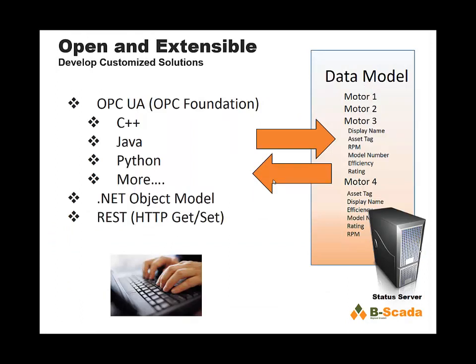What BSCADA has found over time is that once you have this model set up with live data flowing into it, it becomes extremely valuable to an organization. Companies always want to connect to that model with other pieces of software or with custom applications to subscribe to value changes or write information to the model. Because the core of the Status system is an OPC server, you can use OPC foundation libraries to connect to the model in C++, Python, or Java. BSCADA has also developed a .NET object model over top of OPC UA, and you can also use REST to get or set values within the model.